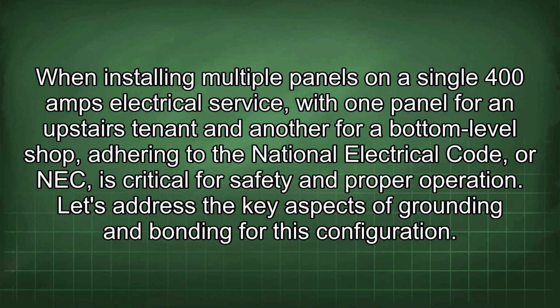When installing multiple panels on a single 400 amp electrical service, with one panel for an upstairs tenant and another for a bottom-level shop, adhering to the National Electrical Code, or NEC, is critical for safety and proper operation. Let's address the key aspects of grounding and bonding for this configuration.